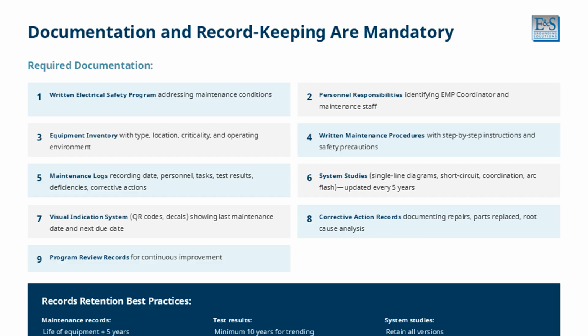Also required: system studies including single-line diagrams, short circuit, coordination, and arc flash analyses updated every 5 years, a visual indication system using QR codes or decals showing last maintenance date and next due date, corrective action records documenting repairs, parts replaced, and root cause analysis, and program review records for continuous improvement. Records retention best practices: maintain maintenance records for the life of equipment plus 5 years, test results for a minimum of 10 years for trending, and retain all versions of system studies.